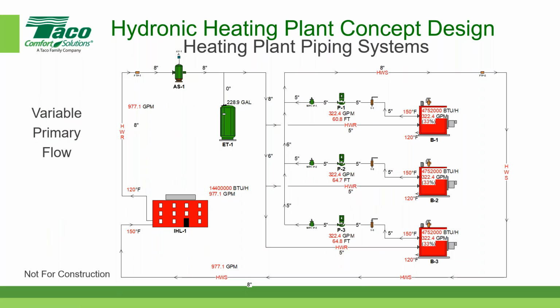How would an outdoor air reset controller affect the piping, or does it? Well, in modern systems, the boiler water temperature is reset based on the outside air temperature. And again, you have to look carefully at the way the boiler is designed to ensure that you're providing a hot water temperature that's both appropriate for the boiler and for the terminal devices in the building. So in our simple example, we have 150-degree supply water temperature. Let's say that the boiler design allows us to vary the supply water temperature from 150. I'm just going to make up a number so you can get an idea of what I'm talking about. Maybe 20 degrees lower, say from 150 down to 130. And that would be based on an outside air temperature reset.